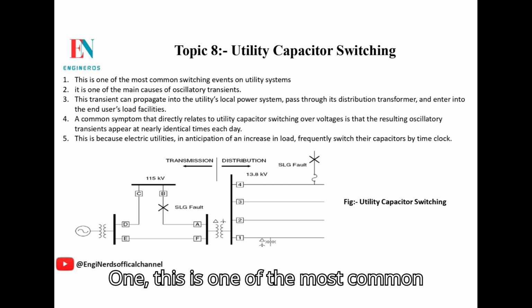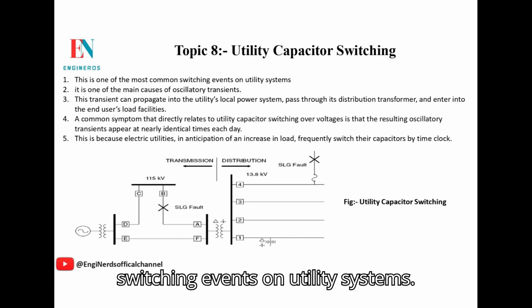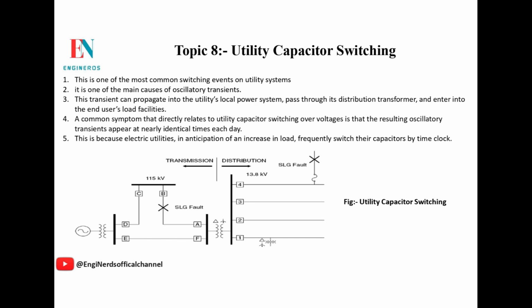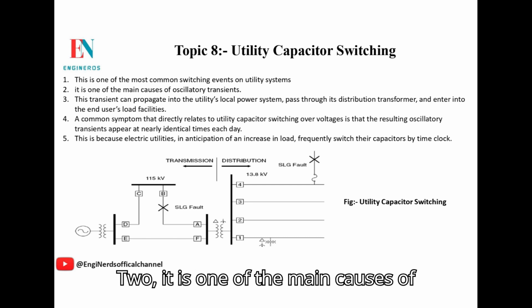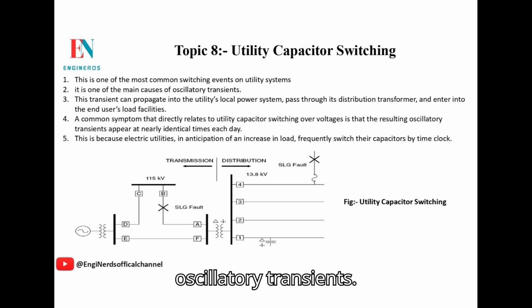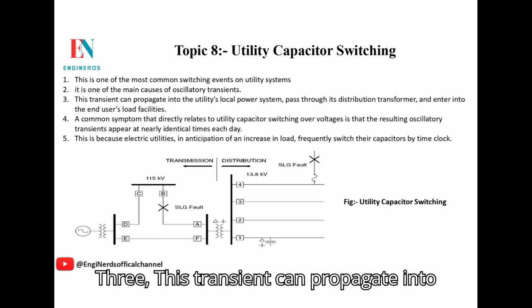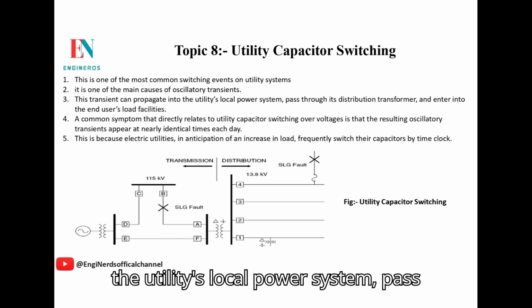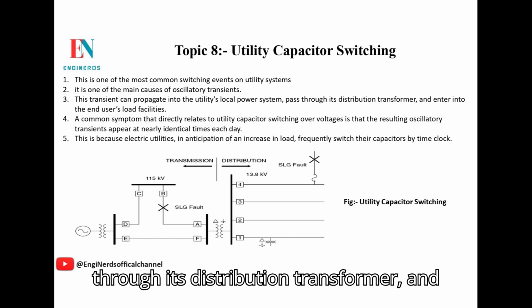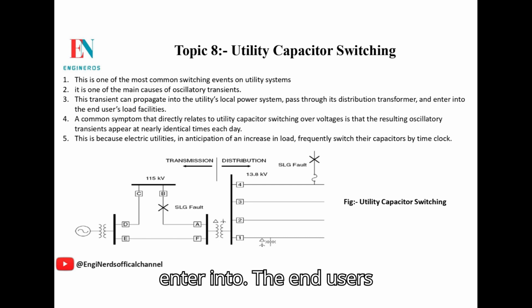Topic 8: Utility capacitor switching. 1. This is one of the most common switching events on utility systems. 2. It is one of the main causes of oscillatory transients. 3. This transient can propagate into the utility's local power system, pass through its distribution transformer, and enter into the end user's load facilities.